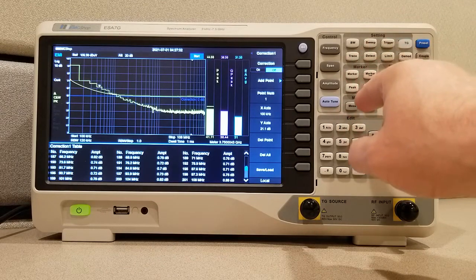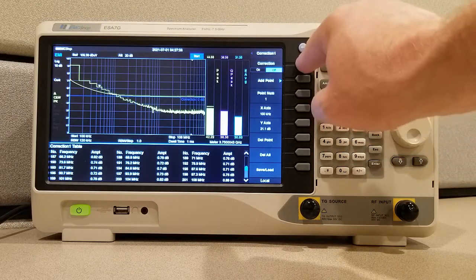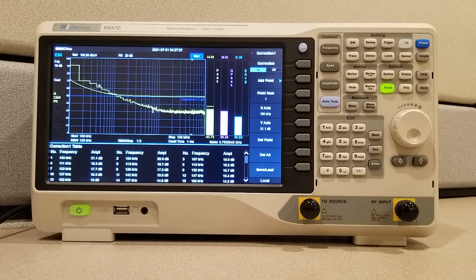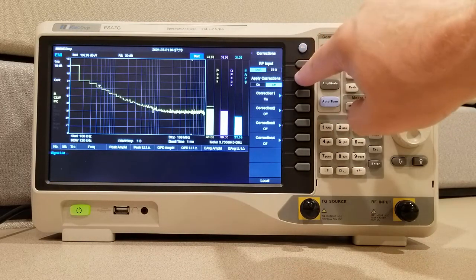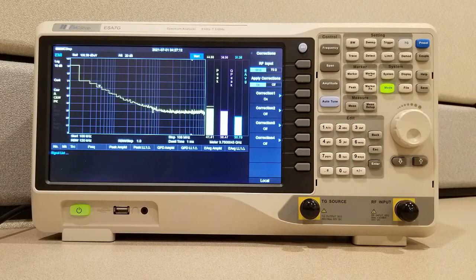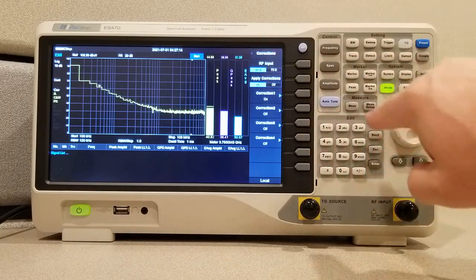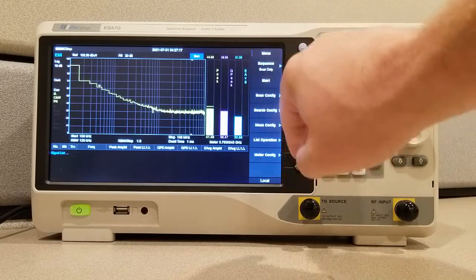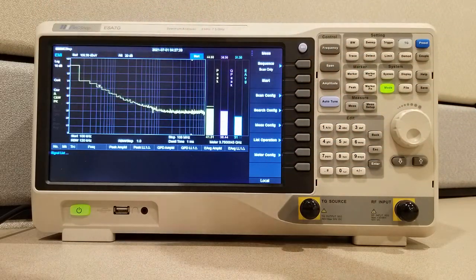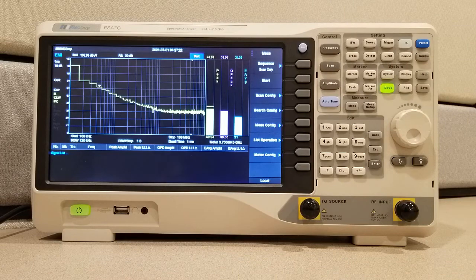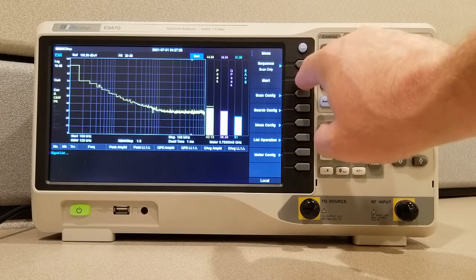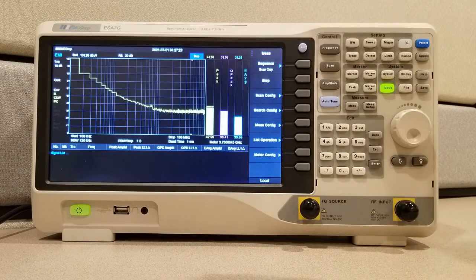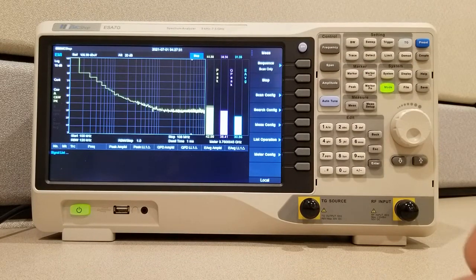And now we are going to do another scan. First we're going to turn the correction on, then we'll back it out, and we have to apply the correction. Now the correction is turned on, it has been applied, we can do a scan, and watch the lower frequencies where the loss is a lot higher, and you will see a pretty good shift. As we start, you see it shifting up for a loss, that's exactly what you expect.